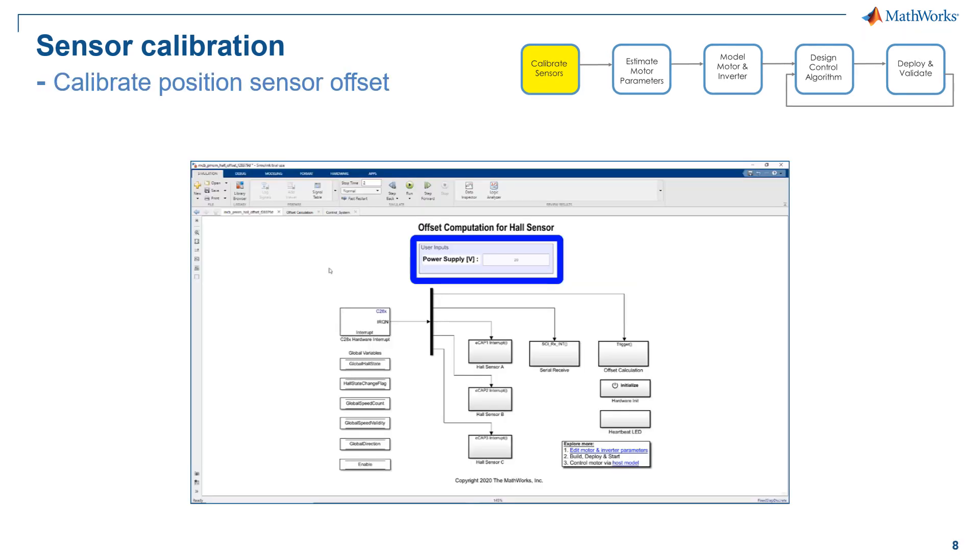Next, we will compute the position sensor offset. The kit that we provide can calibrate for both hall sensor and quadrature encoder. But here we are using hall sensor as an example. For those of you who are interested in sensorless field orientation control, you could definitely skip this step.